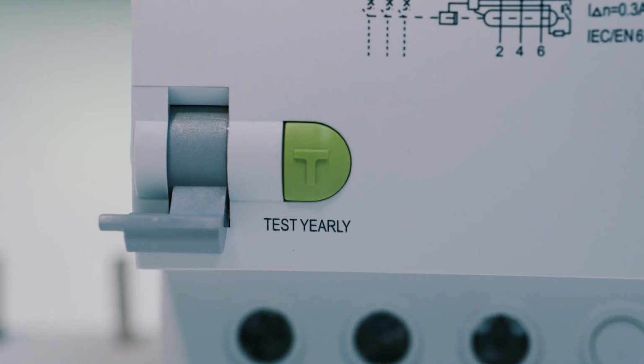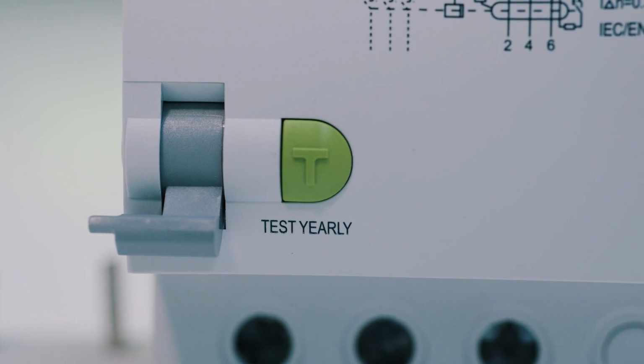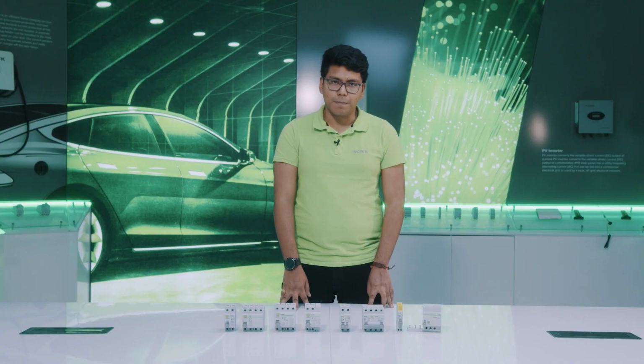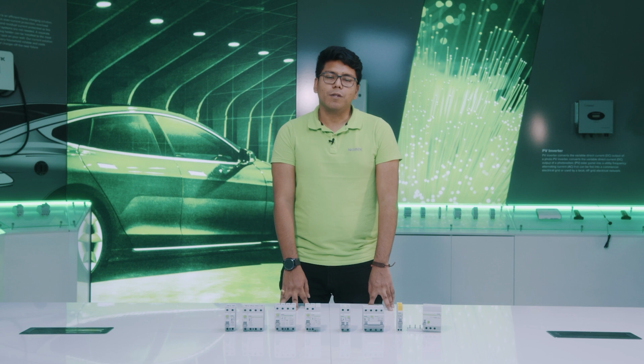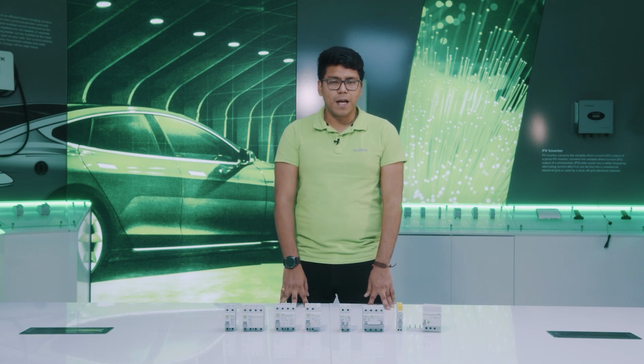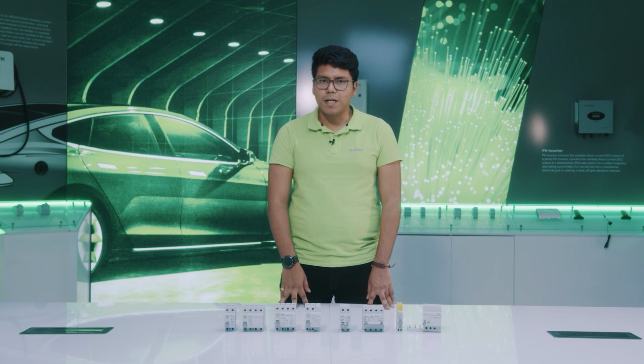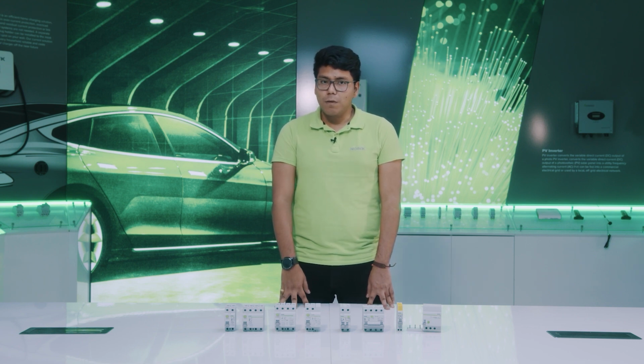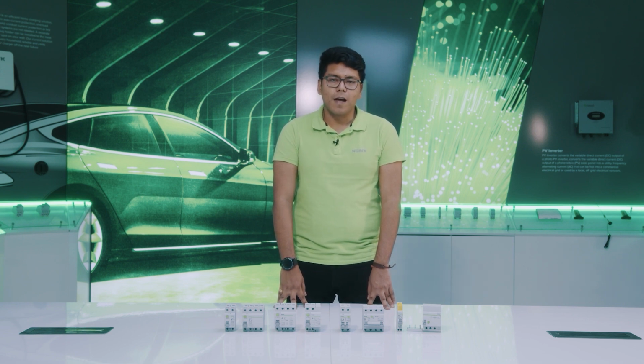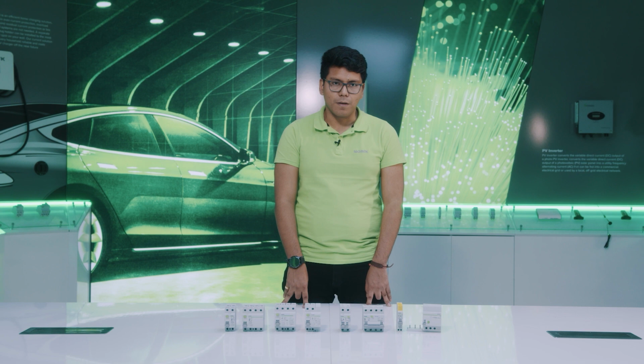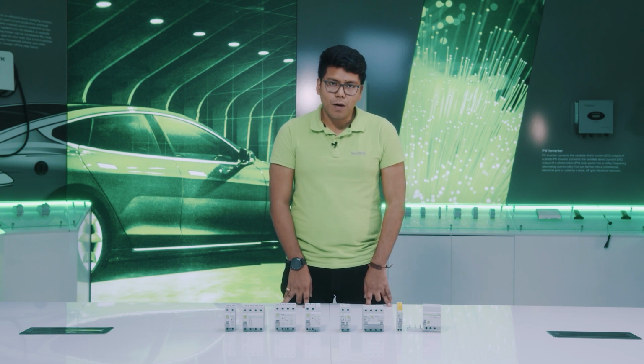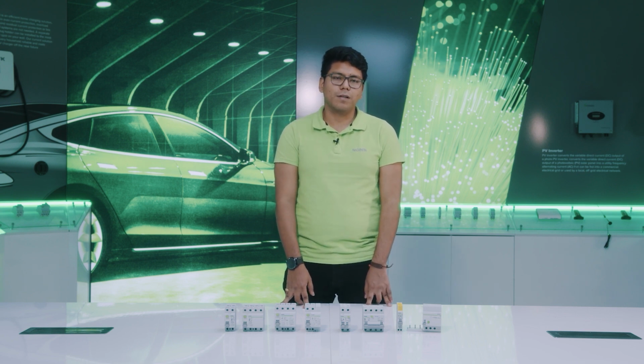The last point is about the testing period. Our magnetic types, RCCBs EX9L and EX9BL, should be tested regularly with a period of 1 month. EX9NL-N and electronic types EX9LB63 and EX9NLA should be tested regularly, but it is recommended to test every 6 months in a fair environment and every month in heavy conditions. Add-on blocks EX9LA have a recommended testing period of once per year. Anyway, please check your local regulations for further details about the regular testing of the RCDs.